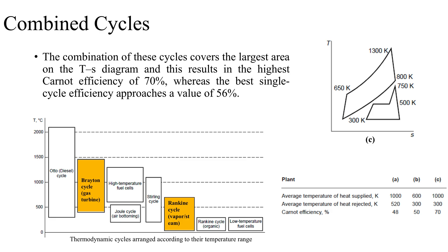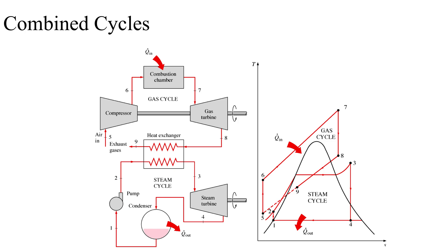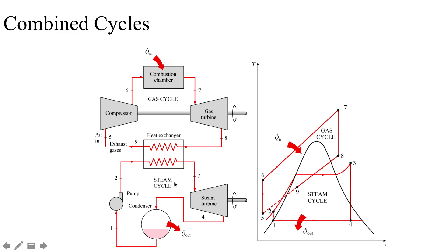The way to combine these two cycles—the schematic for the combined system—includes a heat exchanger in the middle that operates as a heat recovery steam generator (HRSG). The exhaust of the gas turbine is used to heat up the working fluid that leaves the pump from the Rankine cycle. This means the heat exchanger acts as the boiler for the steam cycle. That is the only major difference; all other subcomponents remain the same.